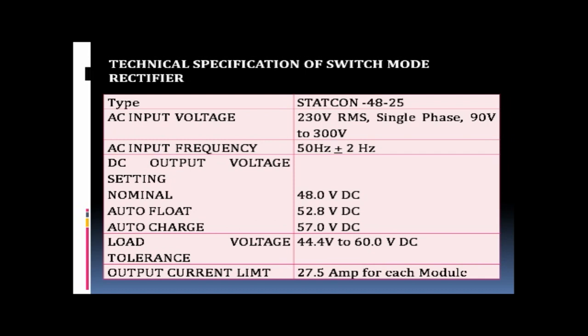DC output voltage setting: nominal 48 volts DC, auto float 52.8 volts DC, auto charge 57 volts DC, load voltage tolerance 44.4 volts to 60 volts DC. Output current limit: 27.5 amperes for each module.